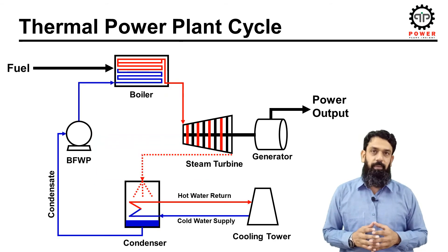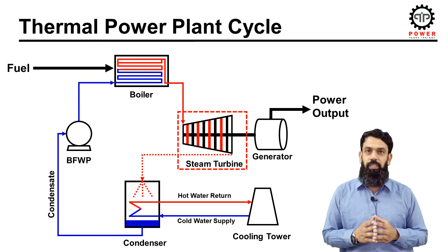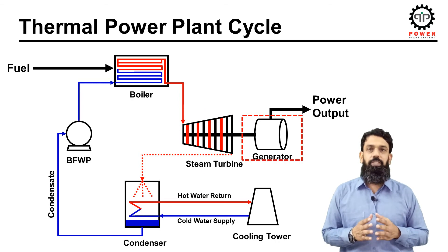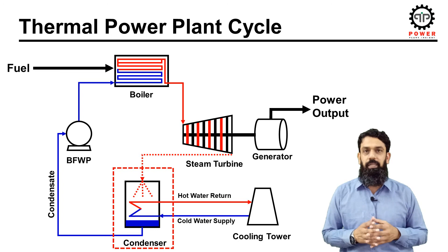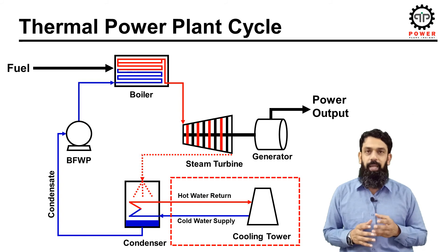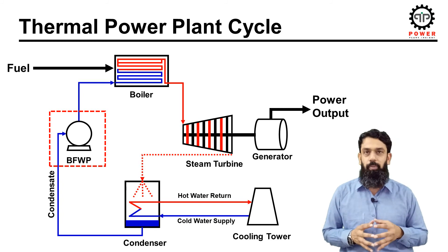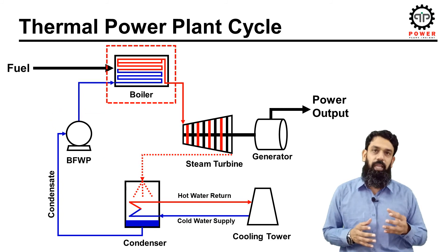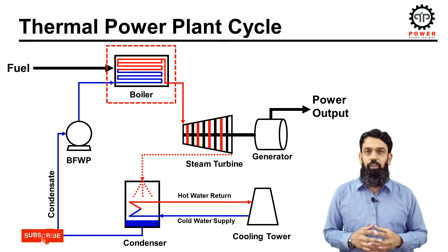Let's summarize today's discussion. Steam is generated in the boiler through combustion of fuel. The steam turbine converts the thermal energy of steam into mechanical energy. The generator converts the mechanical energy into electrical energy. Steam from the turbine enters the condenser where it is condensed; circulating water circulates through the tubes of the condenser and hot water recirculates back to the cooling tower. Condensate from the hot well is extracted through boiler feed water pumps and injected into the economizer section of the boiler, which converts the condensate back into steam — and the cycle continues.